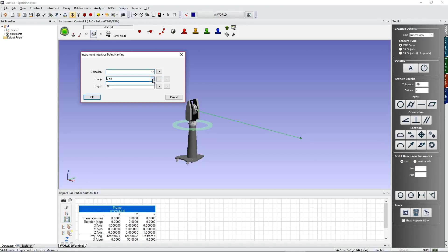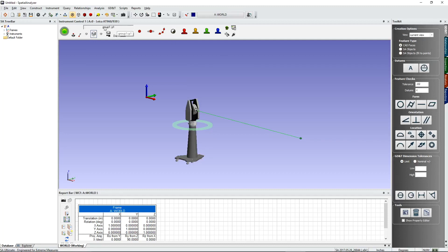You can select a group from the dropdown if you've already shot some points, or just type a new name. Think of the group as the street address and the target name as the house number — each point must have an individual, unique name inside the group, typically starting with P1. Click OK, and to return to this dialog just click in the gray box area of the instrument interface.